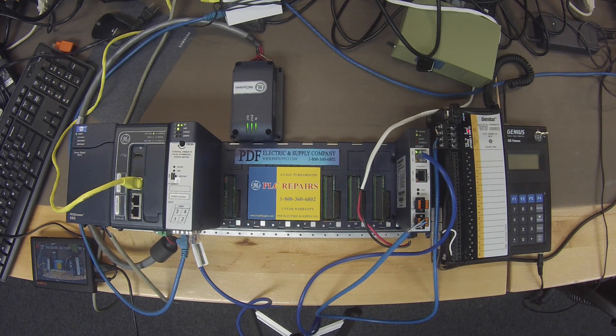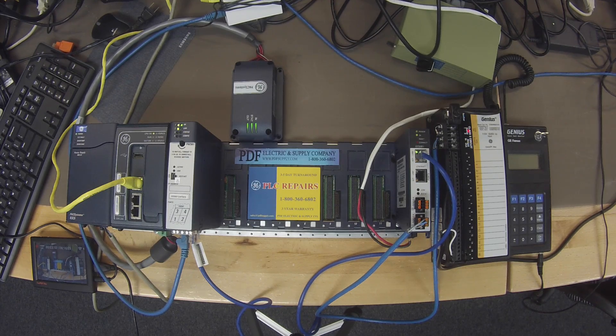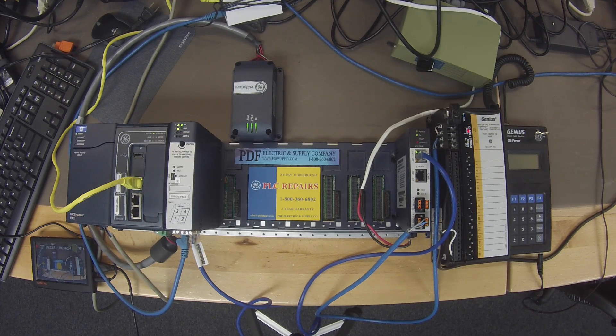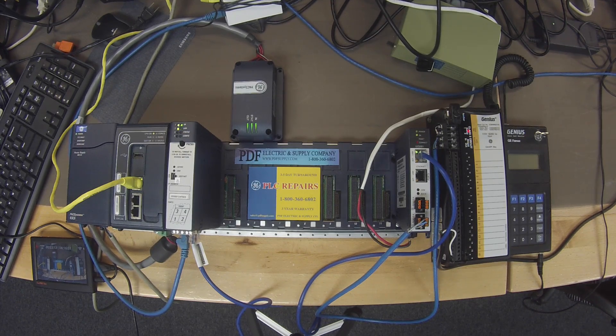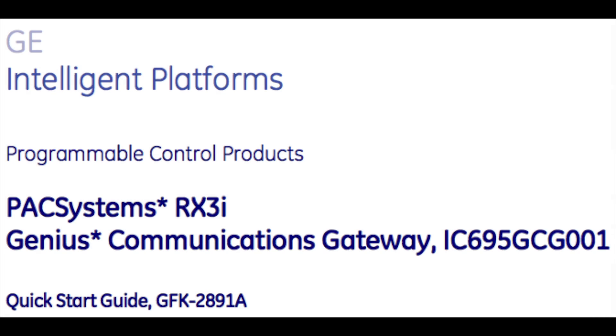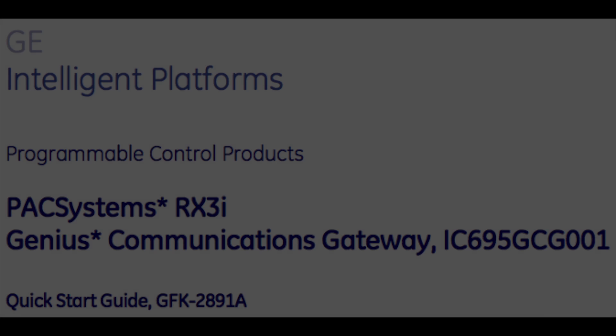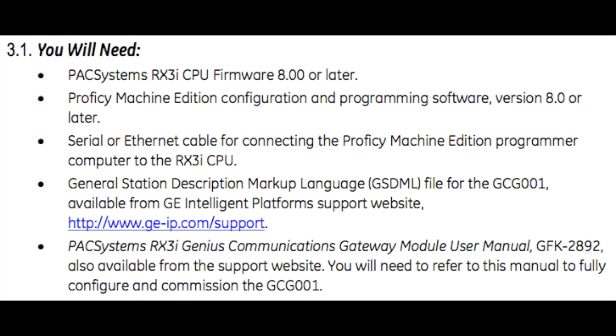So moving on to configuring this, before we start configuring it, I just want to let you know I'm looking in the manual that comes with it, which is the GFK-2891A. And a couple things that are mentioned in here that are very important. You must have an RX3i CPU with firmware 8.0 or later to use this device.